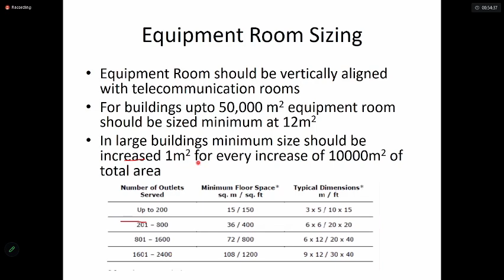Remember, this is a guide for deciding at the design stage how much area should be required for the equipment room, because at the design stage we don't know the exact sizes of the equipment yet. So at the initial design concept, you should allocate the equipment room spacing, and you can use either of these two methods to get an idea of what size equipment room will be required for your building.